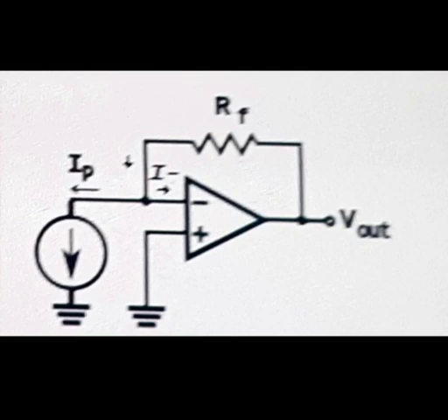A current to voltage converter will produce a voltage proportional to a given current. This circuit is required if your measuring instrument is capable of only measuring voltage and you need to measure current output. If your instrument's data acquisition module has an input impedance that is several orders larger than the converting resistor, a simple resistor can be used for the data conversion. However, if the input impedance of the instrument is low compared to the converting resistor, then use the operational amplifier.